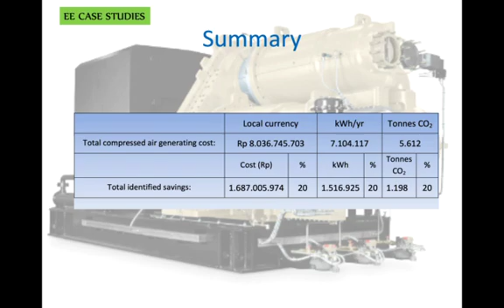What I found is the total identified saving, because we conducted the energy audit here in the compressed air system. From that we identified the total energy saving could reach about 1.5 million kilowatt hour per year. This is equivalent to about 1.6 billion rupiahs. This accounts for about 20% of the energy consumption per year. So from this point, the total identified saving is quite significant, because it accounted for about 20% of their energy consumption per year.